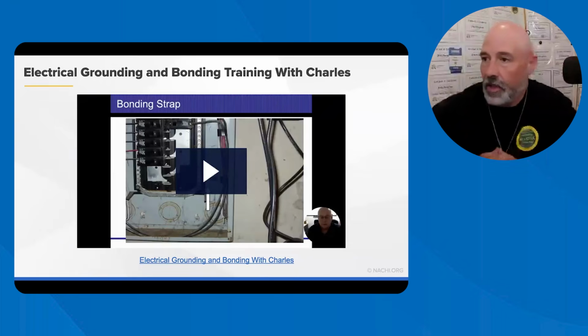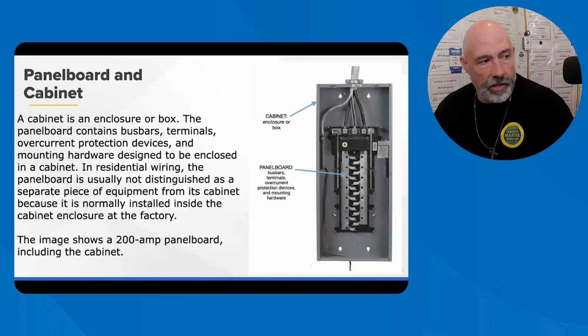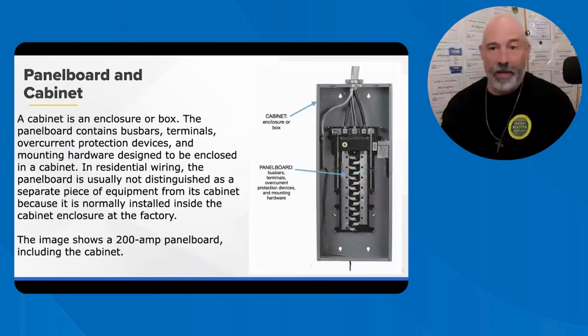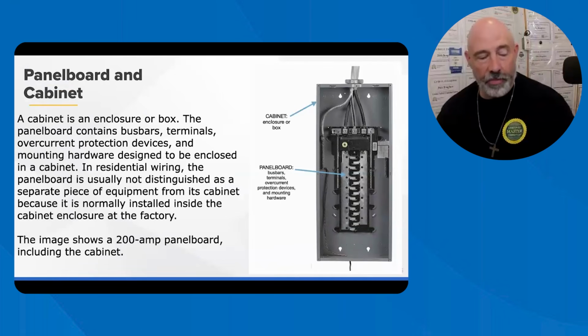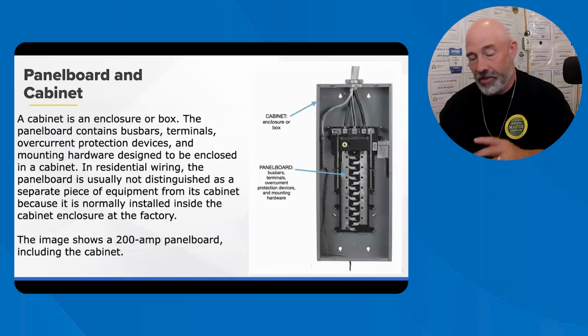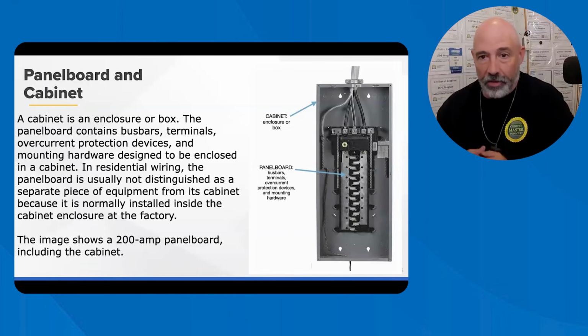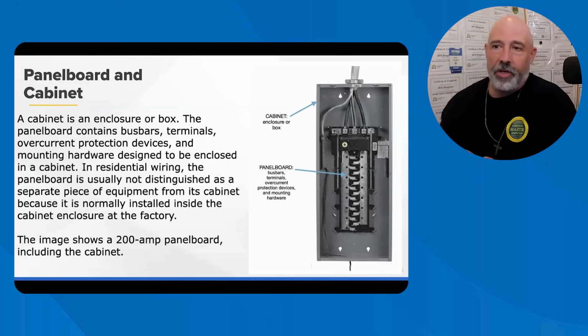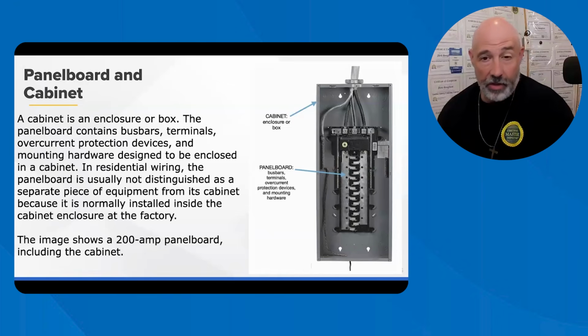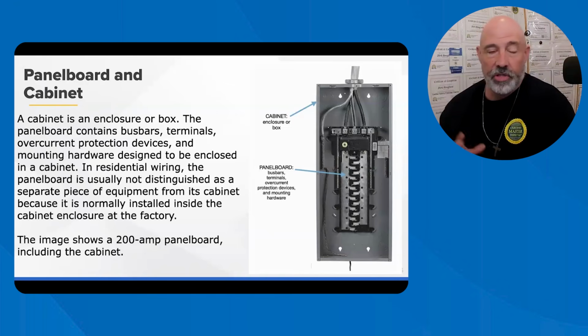I watched this one, and the panel board and the cabinet normally is called the electrical panel, the breaker box, the breaker panel. It contains bus bars. If you don't know what the bus bars is, that is basically where it's traveling. If you think about a bus, it has a bunch of students in there and you can put them in. That's why it's called a bus. And in residential construction, the panel board and cabinet are typically manufactured as one unit. The panel sizes are typically 100 amp service or 200 amp panel. Normally about 40 spaces or so are common.